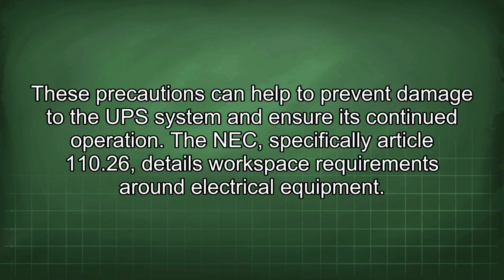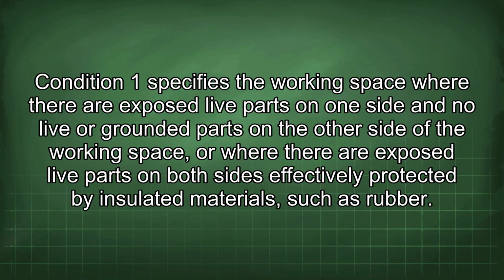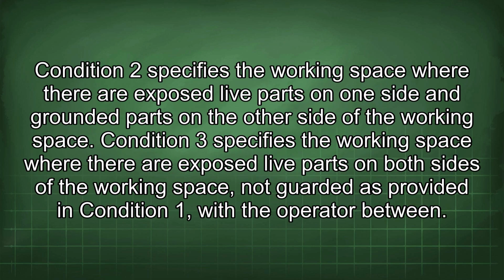The NEC, specifically Article 110.26, details workspace requirements around electrical equipment. Condition 1 specifies the working space where there are exposed live parts on one side and no live or grounded parts on the other side of the working space, or where there are exposed live parts on both sides effectively protected by insulated materials, such as rubber. Condition 2 specifies the working space where there are exposed live parts on one side and grounded parts on the other side of the working space. Condition 3 specifies the working space where there are exposed live parts on both sides of the working space, not guarded as provided in Condition 1, with the operator between.